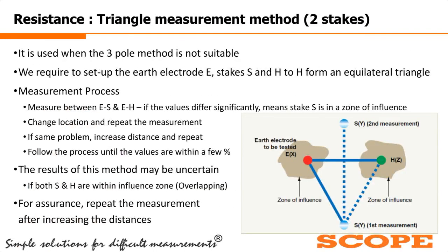Then the next one is the two stake or the triangular measurement method. In this measurement method, we will require two electrodes. First one is the earth electrode which is being tested, called E, and we will require two measurements by using stake S and stake H. So first we will measure the earth resistance between terminal E and S. After that, we will measure the earth resistance between E and H, and these three points E, S, and H must be placed such that a triangle, or an equilateral triangle, is formed.